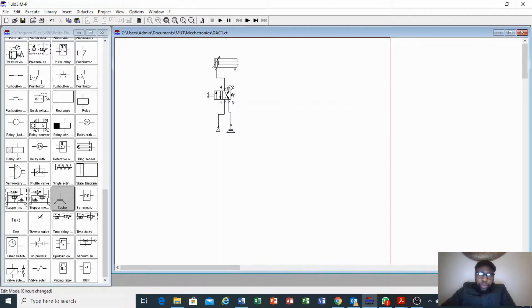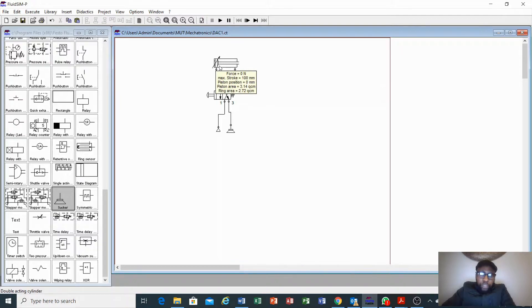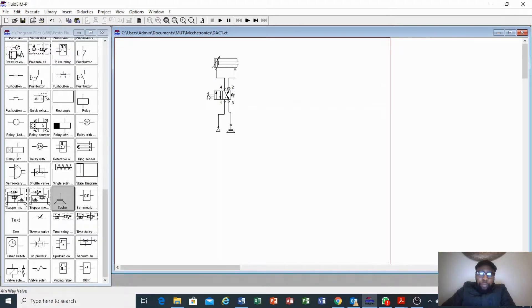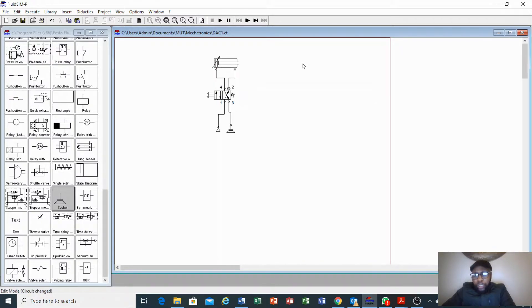Let us connect pressure and let us connect exhaustion. Now, as we can see, this is a double-acting cylinder — a double-acting cylinder will need pressure on this port to retract after being extended. So we need to put pressure to make sure that our cylinder is retracted. Then when you push our push button, we need to put pressure on this side to make sure that our cylinder extends.